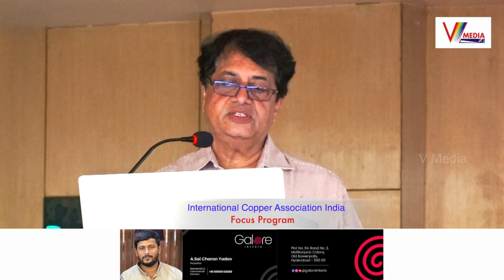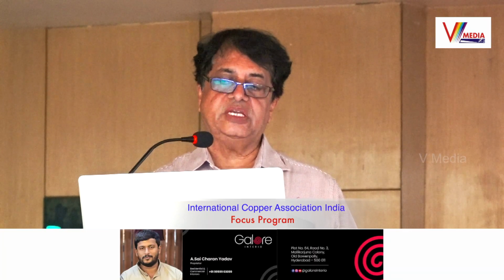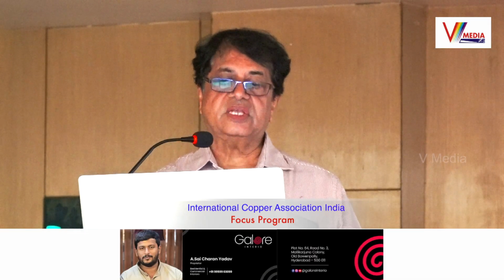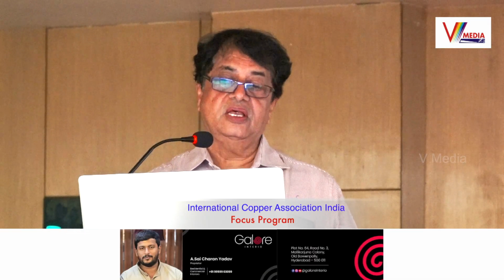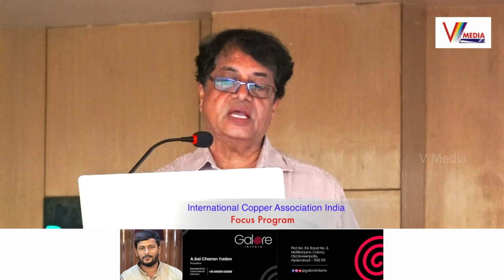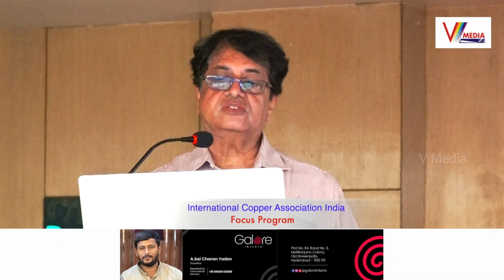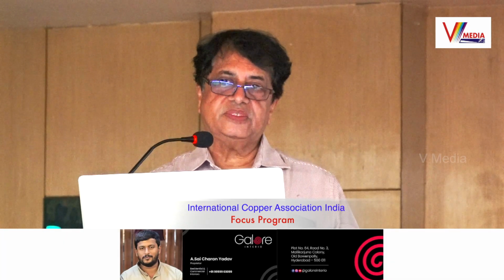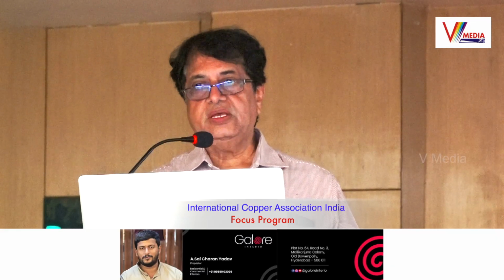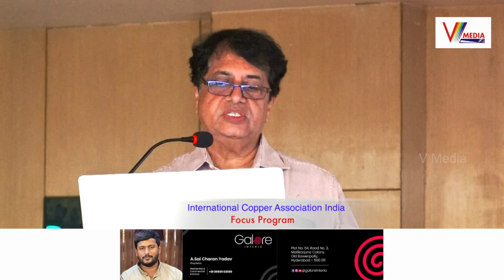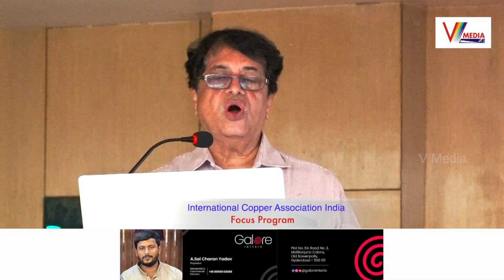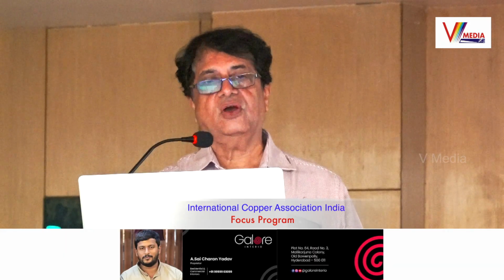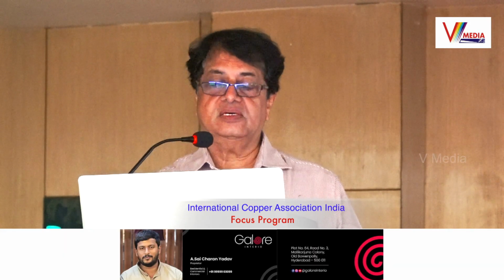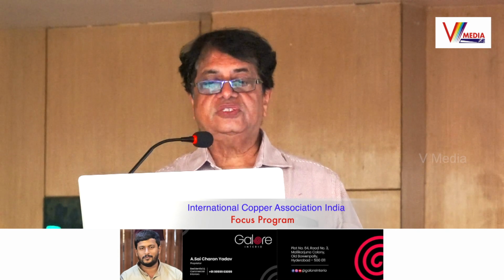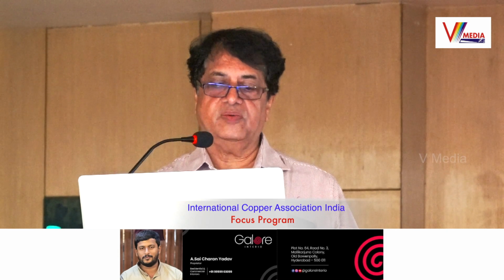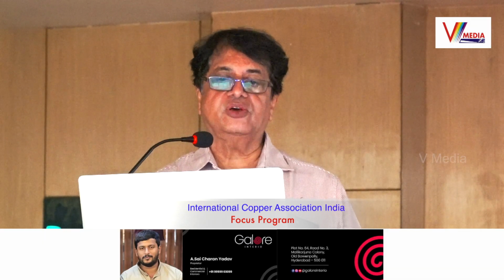And one more thing, you will see here a chamber, we have shown it here, where for the underground cabling, some chambers are required at certain locations. For these chambers, you have to consider the size, and consult with the electrical design consultant. He will tell you the size of this chamber. Why is this size important? In the distribution system, it is necessary that if some fault occurs in the cable, to clear that fault, some additional length of cable is required. So this additional length of cable is coiled here in this chamber. So how much will be the diameter of that coil? Again, there is a calculation for that. The electrical designer will tell you he will require a chamber of such and such size. And of course these chambers have to be accessible all the time. Whenever some fault occurs, it should be accessible. It should not get concealed within your paver block or something like that.